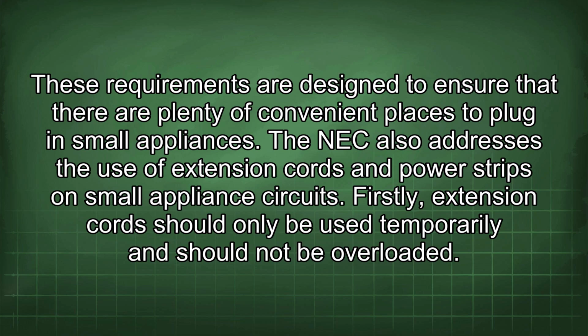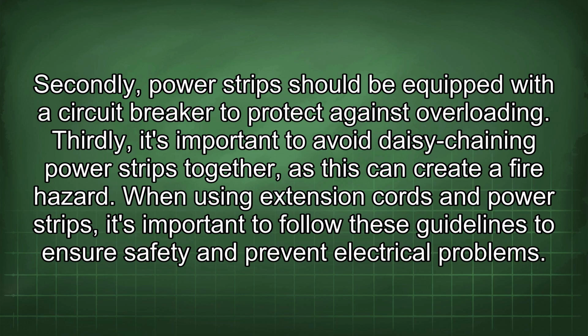Firstly, extension cords should only be used temporarily and should not be overloaded. Secondly, power strips should be equipped with a circuit breaker to protect against overloading. Thirdly, it's important to avoid daisy-chaining power strips together, as this can create a fire hazard. When using extension cords and power strips, it's important to follow these guidelines to ensure safety and prevent electrical problems.